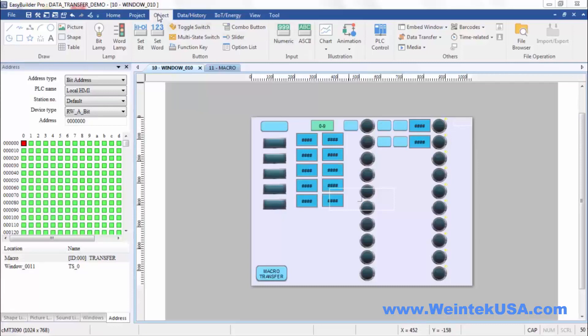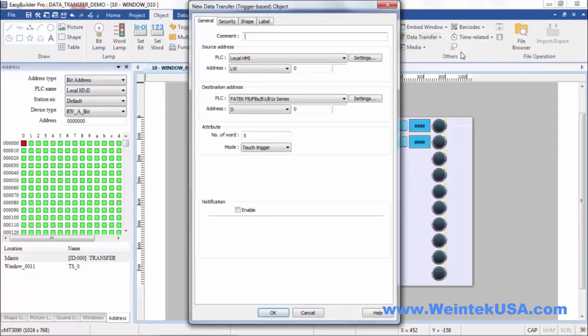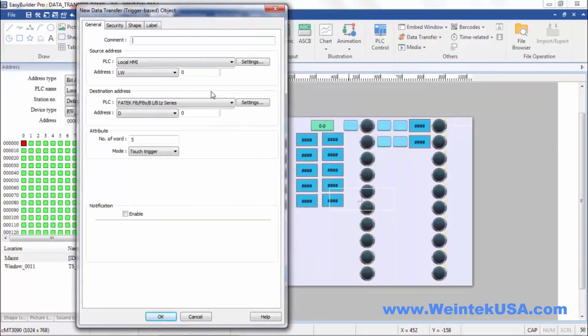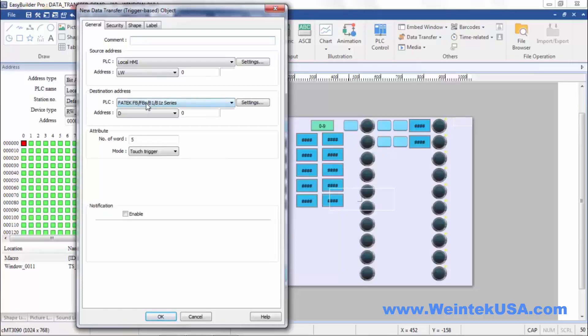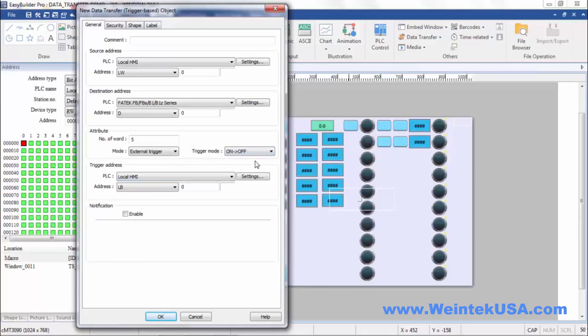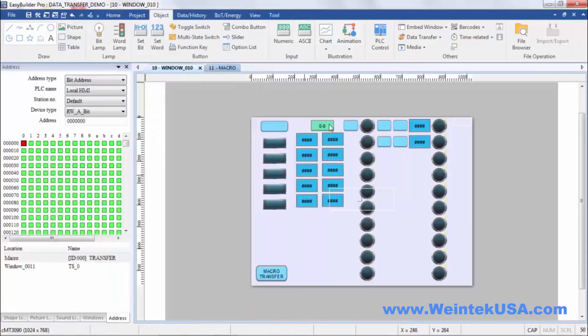If you go to the object tab and find data transfer, you'll see two types. First type we're going to discuss is a trigger-based data transfer. Here you can see we are taking data from LW0 and our destination register is our FATEK PLC D0, number words 5. This is a touch trigger, but you could also use an external trigger which would be a PLC or HMI local bit, and you can define the trigger state.